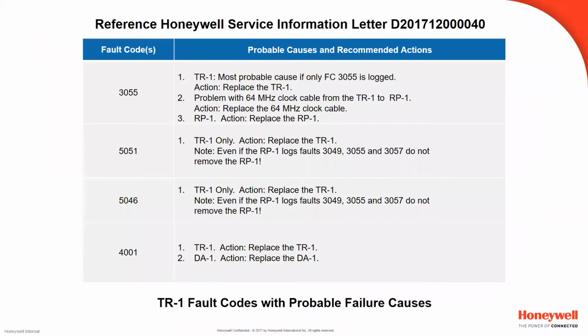Yeah, and we saw earlier that a 3055 fault getting logged was due to formatted pulse data message received for 2 seconds when the radar was in transmit mode. And when a 3055 is logged with the 3716, then it's RP faulty. But in this case, we say that only if a 3055 is logged, then it would be most likely a TR faulty and not the RP.